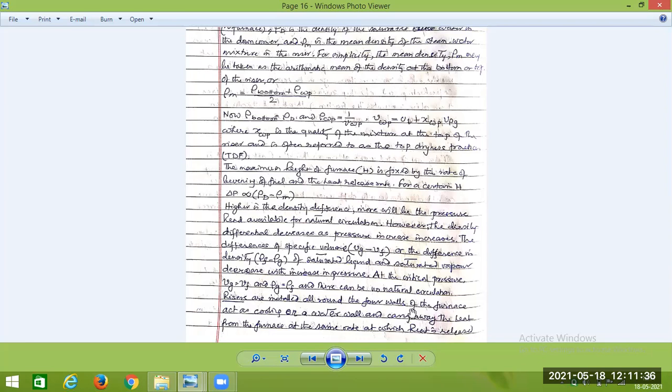For these reasons, adequate circulation must be given in the circuit itself. If the circulation is not adequate, the rate at which heat is carried away will be less than the rate of heat release itself. So you have to burn more fuel, but you are not getting the proper use of it. The difference will be stored in the metal of the tubes, leading to voids and ultimately rupturing when the tube temperature exceeds the melting point of the metal.